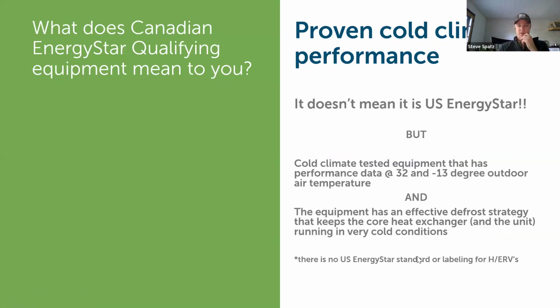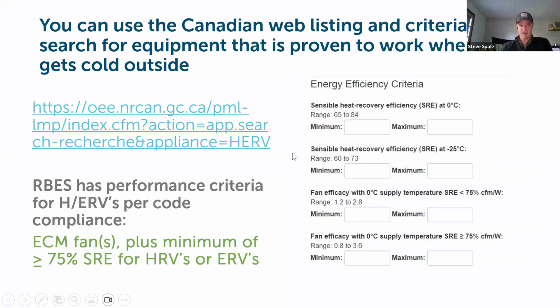One of the other key things that comes out of the Canadian requirements for the listing is that there is a defined and effective defrost strategy for the heat exchanger, because once you're pulling cold air into that core, if it's going to get frozen or frosted up, there needs to be a functional way for that core to defrost or warm back up. Depending on the manufacturer, they may have an active electric resistance coil that preheats the air going into the core below a certain outdoor temperature, or you'll have systems that recirculate the exhaust air through the core to defrost it if it does get to that point. So there are different strategies manufacturers use to keep the core functional when it's really cold outside.